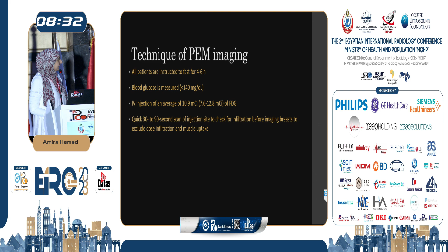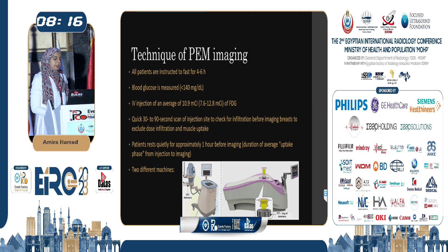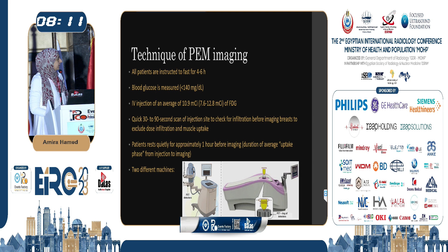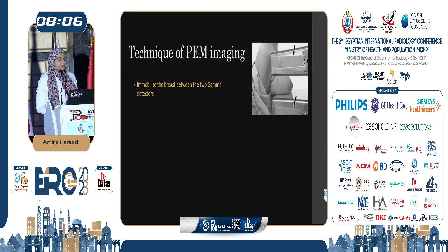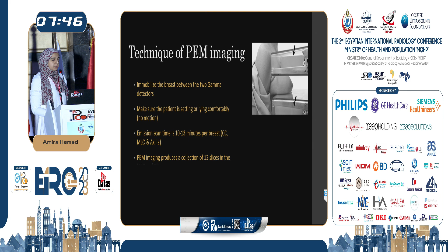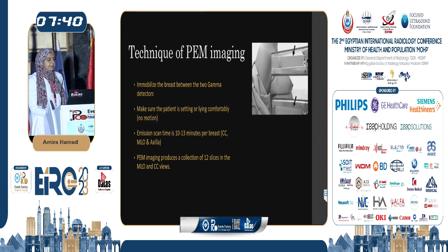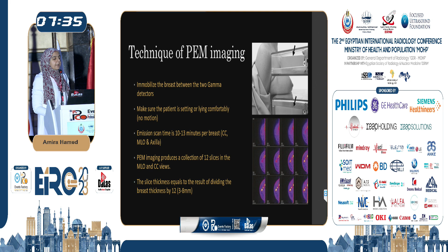The patient rests quietly for 1 hour, then she is subjected to the imaging, either on a vertical machine that's similar to a mammography machine, or another machine where the patient lies supine in the detector. Then we immobilize the breast between the detectors, making sure she's not moving and she's sitting comfortably, because the examination will take a bit of time, as each position can take up to 5 minutes. So it's a total of 10 to 13 minutes for each breast. Then the images are displayed in a collection of 12 slices of MLO and CC views. The slice thickness is equal to the breast thickness divided by 12.